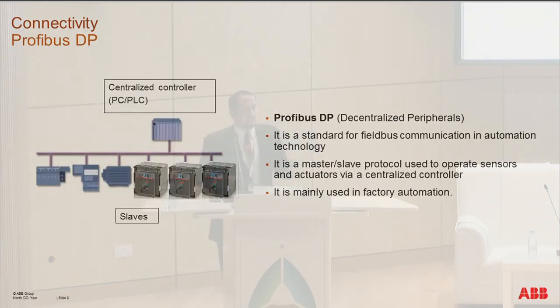Profibus DP is actually used for supervision and controlling the system. It's based on the master-slave architecture, and the application is mainly used for factory automation. Again, it's integrated in the ABB Emax2 air circuit breakers without the need of any external converters, and for the molded-case circuit breakers, it's integrated without the need of any external converters.